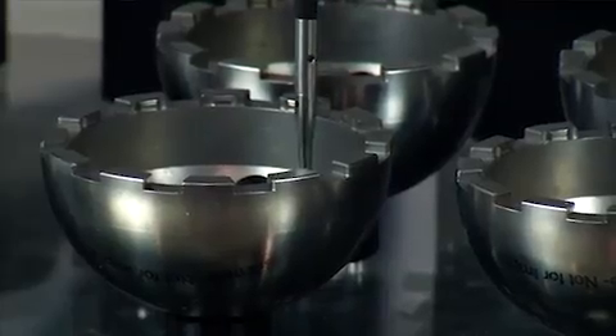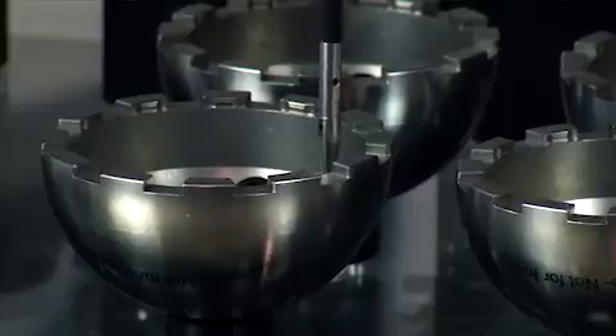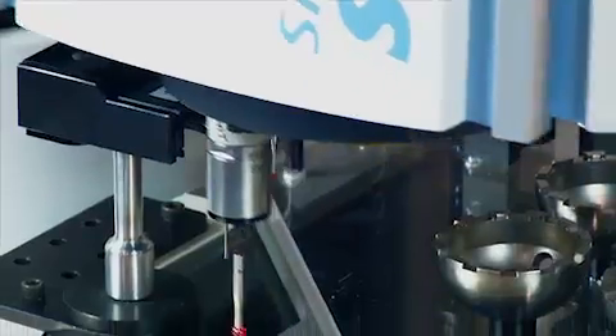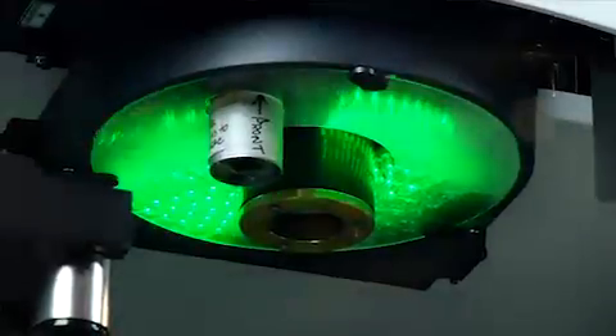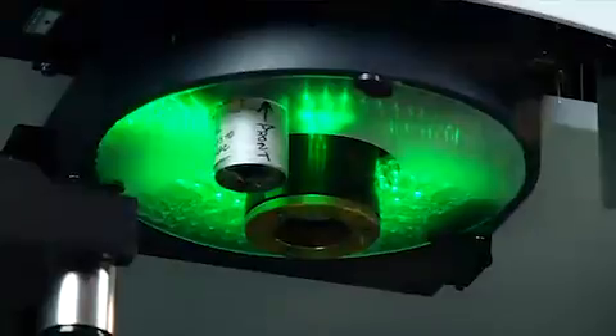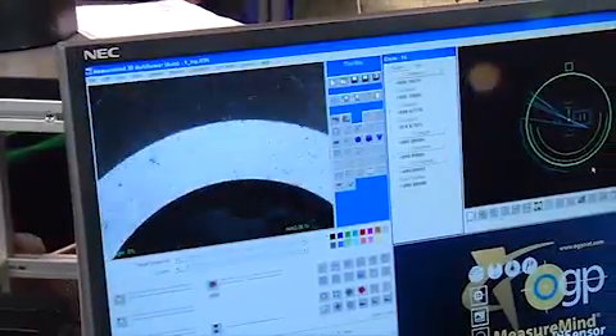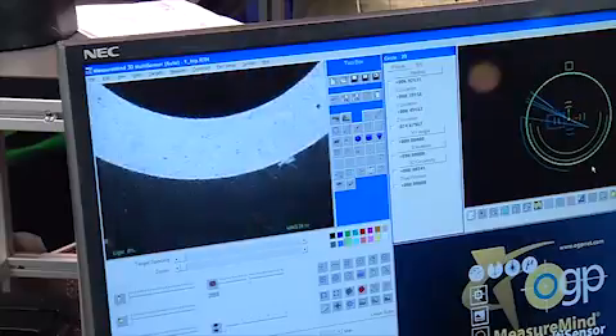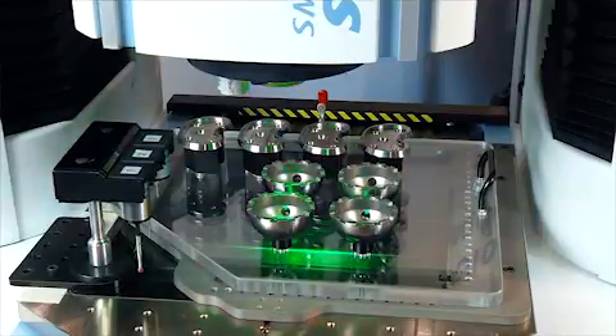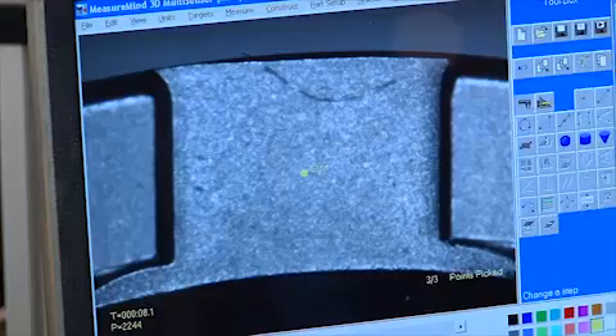Here it's doing multiple scans on spherical and cylindrical surfaces to establish cylindricity, taper, sphericity, and the relationships between the geometries. Docking the probe now, putting the probe away so it has room to use laser and video. Here it's using video to make multiple video measurements. The video tool is good for measuring change in contrast, so where surfaces meet, which are typically defined by some geometries that are lines, circles, arcs, and curves. Now, the laser is good for measuring surfaces, for acquiring data on unknown contours or known contours to establish planes, surfaces, and the Z heights in particular.